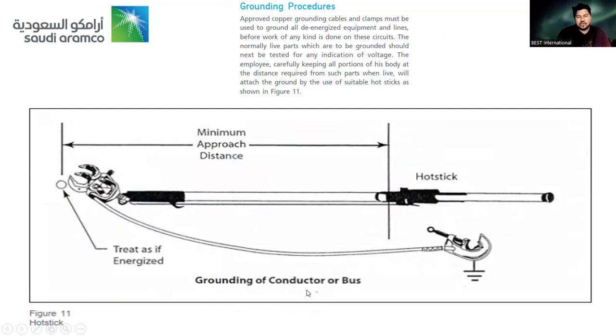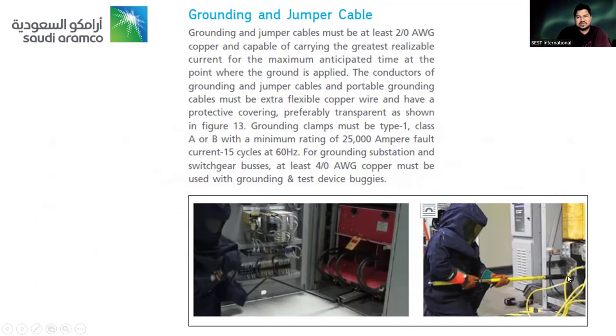This is just another grounding of conductor or bus. How do we ground it? And sometimes not only one point, we have different points of grounding to make sure that we are safe all the way. Grounding or jumper cable, this is just an example. Grounding or jumper cables must be at least 2/0 AWG copper and capable of carrying the greatest anticipated fault current for the maximum anticipated time. Okay, so 15 cycles at 60 hertz has 25,000 amperes fault current. For grounding substation switch buses, at least 4/0 AWG copper must be used with grounding and test device.